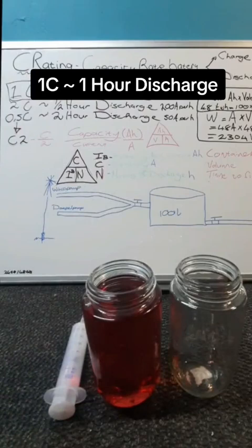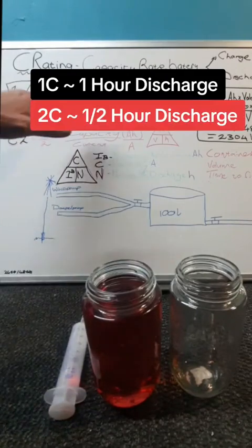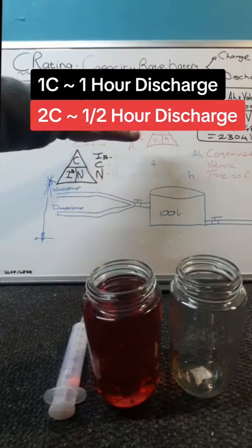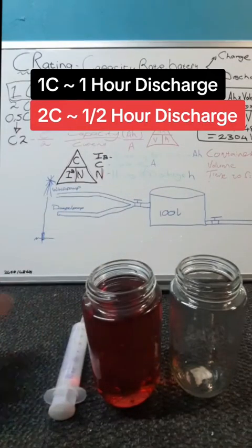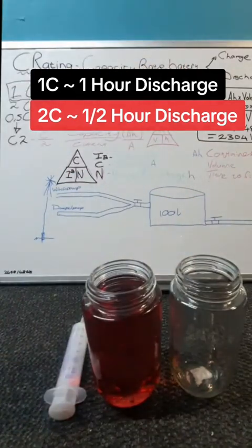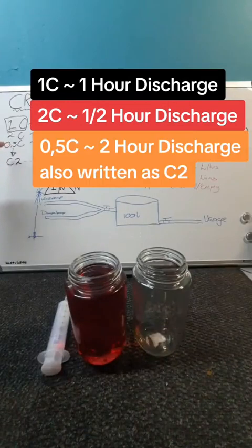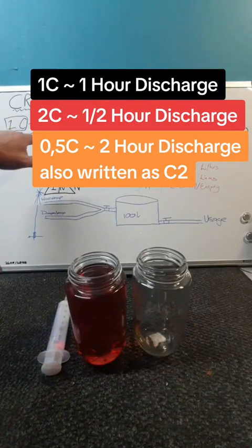We're going to look at a few examples. Then a 2C battery basically means that in a half an hour you can charge and discharge the battery. I put it here basically on a 100 amp hour battery. Then you get sometimes they will write 0.5C and that says to you two hours discharge and two hours charge.